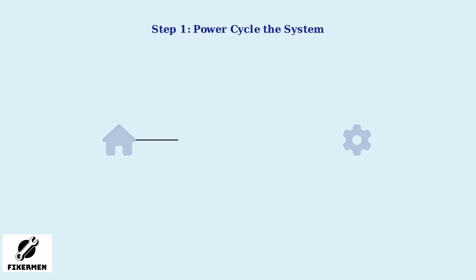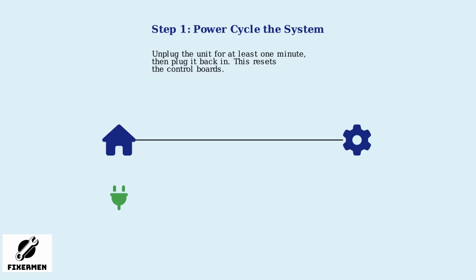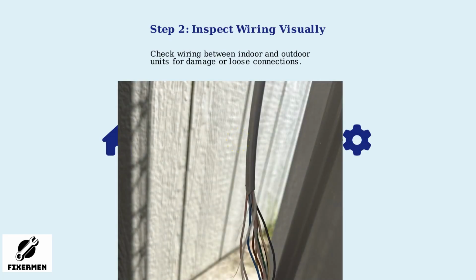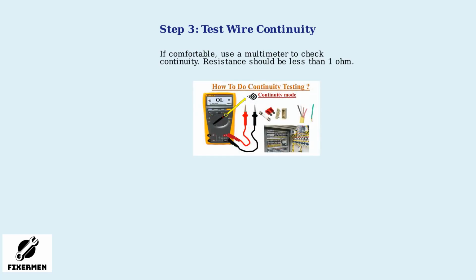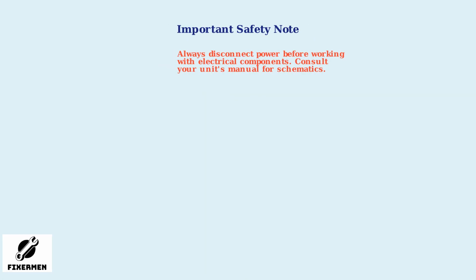Before calling a technician, try these simple steps. First, power cycle the system. Unplug the unit for at least 1 minute, then plug it back in. This can reset the control boards. Next, visually inspect the wiring between the indoor and outdoor units for any obvious damage or loose connections. If you're comfortable, use a multimeter to check wire continuity. Resistance should be less than 1 ohm. Always disconnect power before working with electrical components and consult your unit's manual for specific schematics.